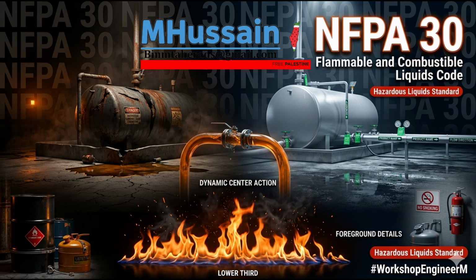Yeah. Why does NFPA discourage venting a box of fumes? It feels wrong, I know. But you have to view the cabinet through the lens of a fire scenario, not just daily operations. Its only functional purpose in an emergency is to be an unbroken thermal envelope. Yeah. If you drill a hole in the top and bottom for a standard vent, you just compromise the envelope. You made a pathway for fire to enter. Because if the vent duct isn't fire-rated, it just melts away. Right. And you've installed a chimney on your fuel source. Exactly. The intense updraft of a warehouse fire will literally suck the flames right through those vent holes and into the cabinet, instantly boiling the contents.